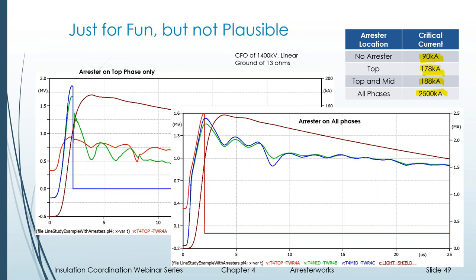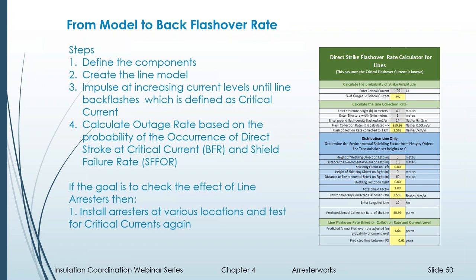I really have to question whether I have a top and middle, because the middle should be, oh, I know, I put it just on one side. So if I put it on just one side, then to ground, it doesn't protect both sides, even though it's there at the same location. So I put two arresters on, got me 188 kA, and then if I put three arresters on, it gave me 2,500 kA. I always refer to that as infinite CFO when we have that.